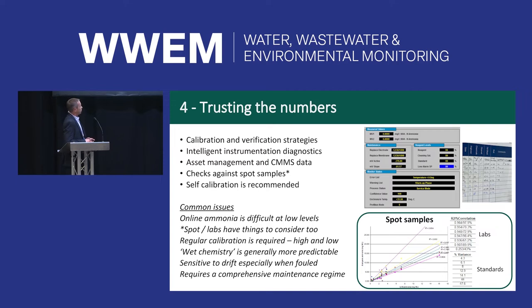For this type of equipment, anything that can self-calibrate to help us understand the data remotely is a good thing for us. For that reason, for on-site installations we tend to standardize on wet chemistry analyzers, because they provide the ability to run an auto-cal at predetermined intervals. We find ammonia needs a high and a low cal to wake it up and check it at low levels as well, which we get with a lot of the wet chemistry equipment we use.